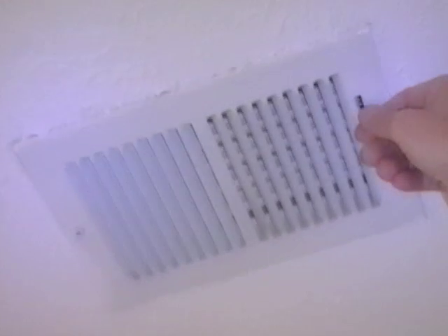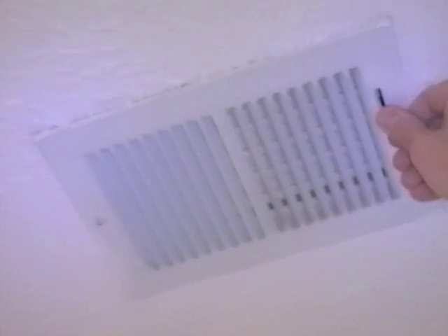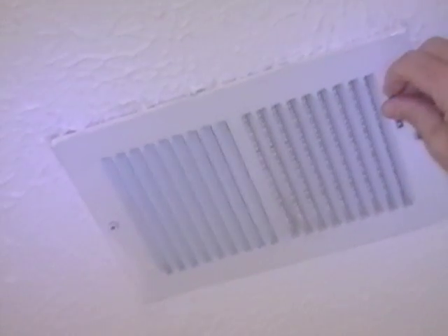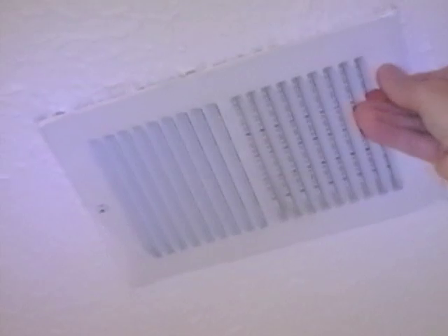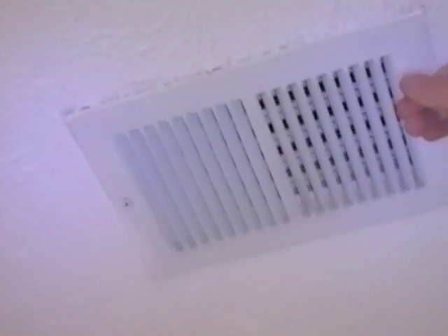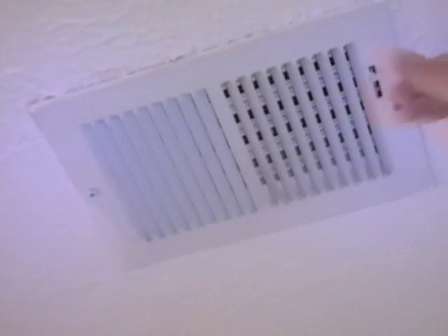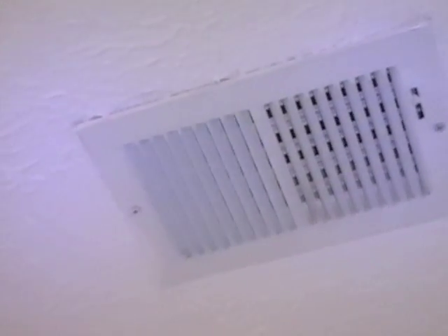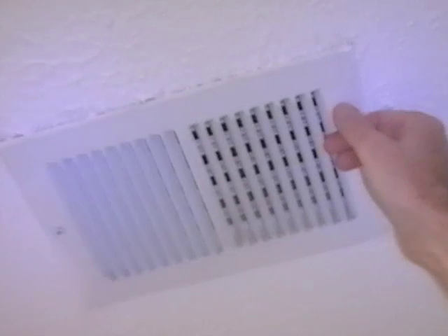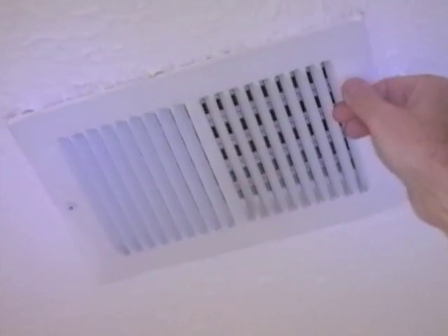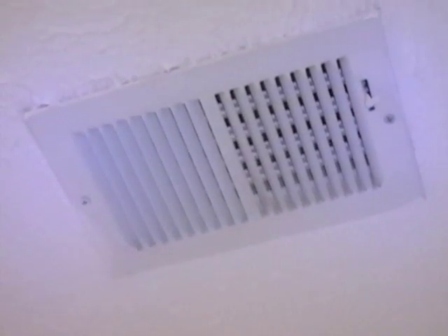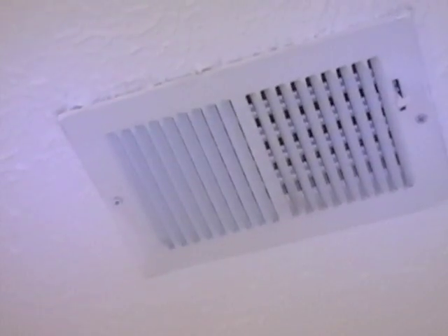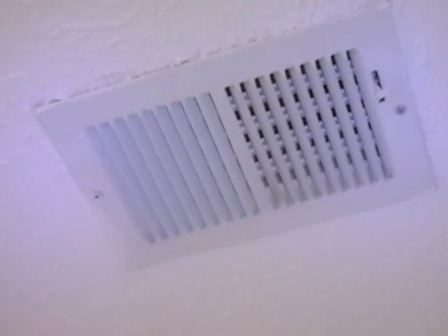This is the registers we're talking about. We're in the basement, so in this case I'm going to close them 3/4 of the way. I'm going to go around to the whole basement and do that. On the main level, I'm going to leave them halfway open. That way I get some airflow there. And now on the top floor, it's winter time, all the air is being pushed up there. I'm going to open them all the way. So I spend most of my time on the upper level. I spend maybe half my time on the main level, and I spend very little in the basement.